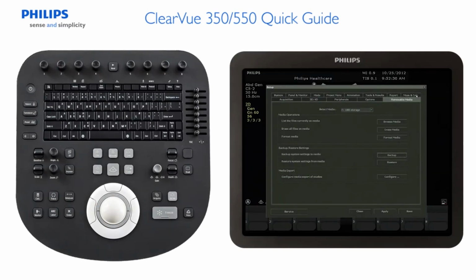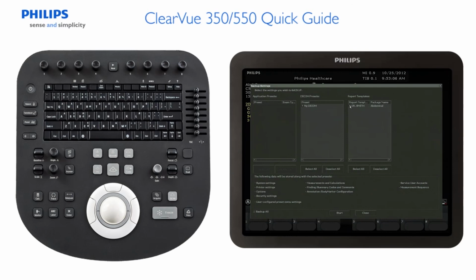On the Removable Media tab, you can browse files on the media, format and erase files on media, backup system settings to a media, and restore system settings from a media. You can also configure export of studies to media such as DICOM or PC format. To perform a system backup, insert a DVD or USB device into the system. Select the preferred media from the Select Media drop-down menu. Click Backup. Select the settings you wish to back up and click Start.